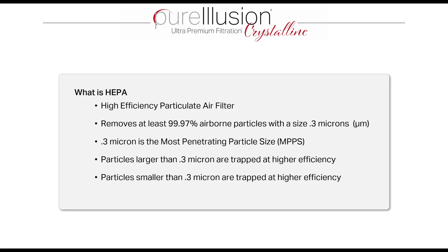0.3 microns is the most penetrating particle size, meaning the size of particle most able to penetrate a HEPA filter. Particles larger than 0.3 microns are trapped at an even higher efficiency rate, and particles smaller than 0.3 microns are also trapped at a higher efficiency rate. So 0.3 microns is the particle size most able to make it through a HEPA filter.